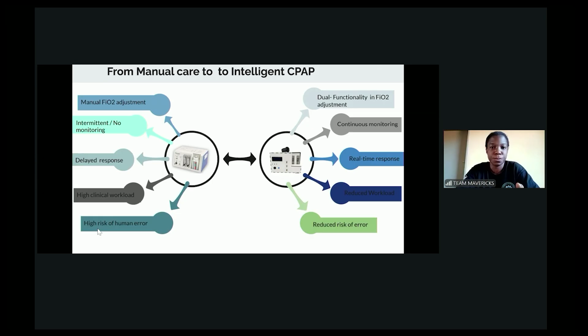To validate and evaluate the performance of the device, we conducted bench testing under controlled conditions, where the system demonstrated successful flow control and wireless transmission, confirming proof of concept and technical feasibility. However, sensor accuracy remains a limitation, with errors exceeding 5%, primarily due to limited filtering, calibration, and signal processing, which we've identified as key areas for further development.